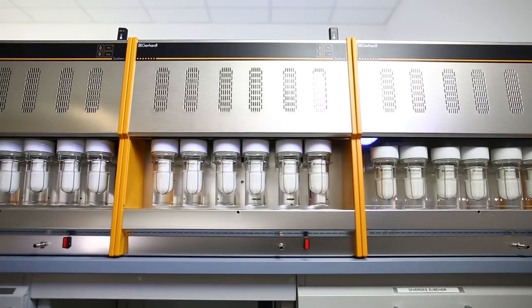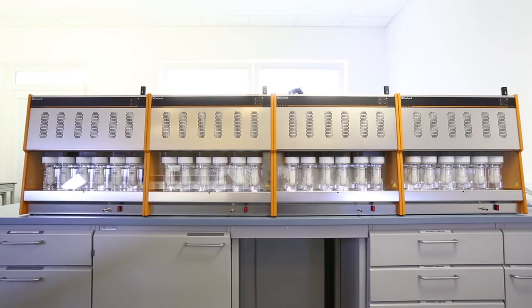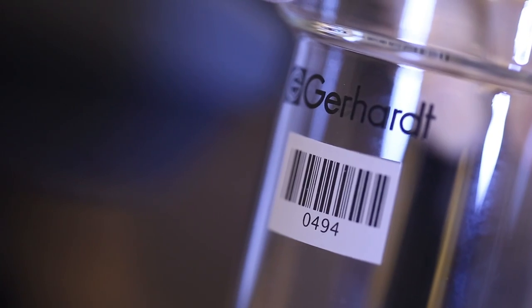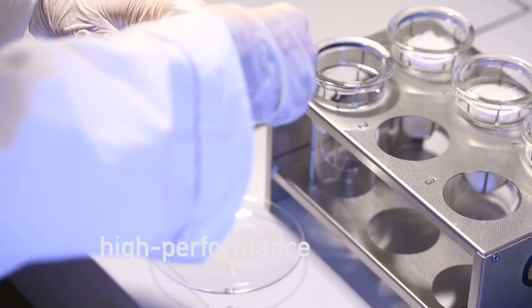Up to four individual instruments can be combined and controlled at the same time. This means that up to 24 samples can be extracted simultaneously.